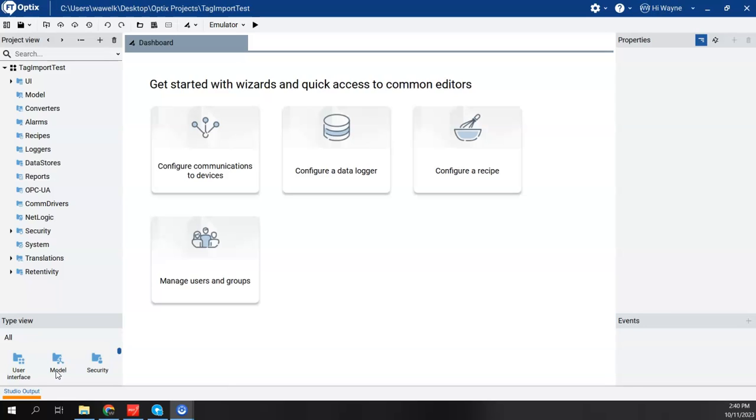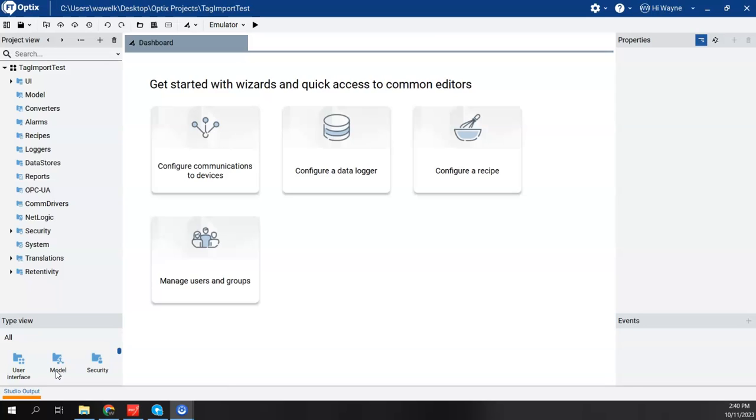But it turns out that if I'm going to connect Optix to a real physical controller, be it a Control Logix or a Compact Logix, that route might actually vary. If we're going to access a Compact Logix or a Control Logix CPU that has the embedded Ethernet port in the CPU, then our route will simply be just the IP address of that CPU.